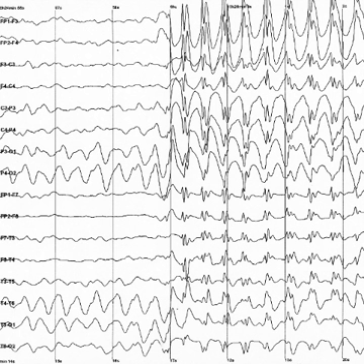During inpatient epilepsy monitoring, a patient's typical seizure medications may be withdrawn. The digital EEG signal is stored electronically and can be filtered for display. Typical settings for the high-pass filter and low-pass filter are 0.5 to 1 Hz and 35 to 70 Hz respectively. The high-pass filter typically filters out slow artifact, such as electrogalvanic signals and movement artifact, whereas the low-pass filter filters out high-frequency artifacts, such as electromyographic signals.